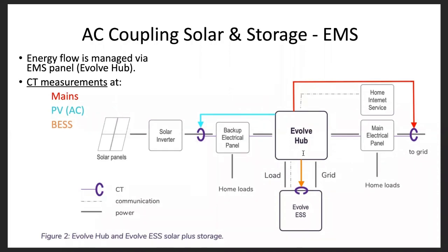Another quick look here as far as AC coupling, solar, and storage. The control and the operation is based on the EMS, the energy management system. The energy flow is managed by the EMS panel or the Evolve hub. The way that we do that is pretty basic: we take some CT measurements, primarily at the main electrical panel, at the point of common coupling, at the service panel near the meter, and measure import export. We also measure PV production, and do a quick add or subtract. The difference between PV production and import export either tells us that there's an excess of loads or an excess of PV production. And then we tell the battery to either charge or discharge and monitor that charge or discharge from the battery CTs.